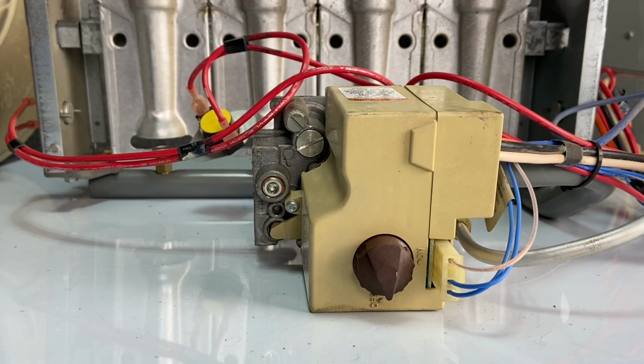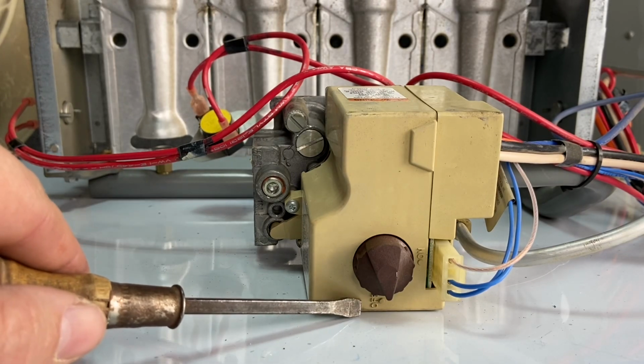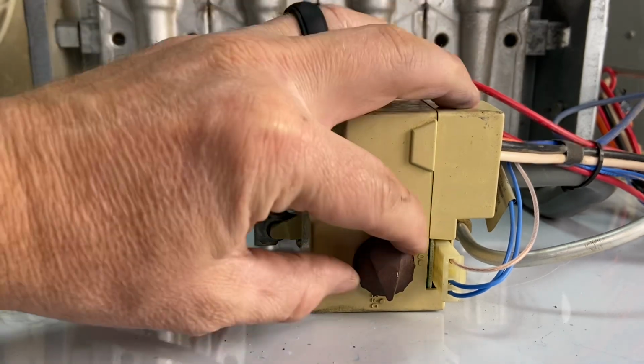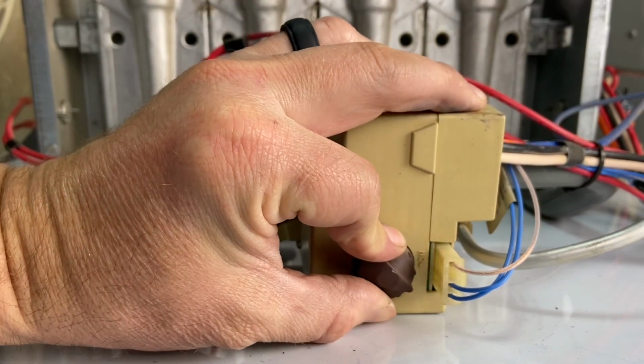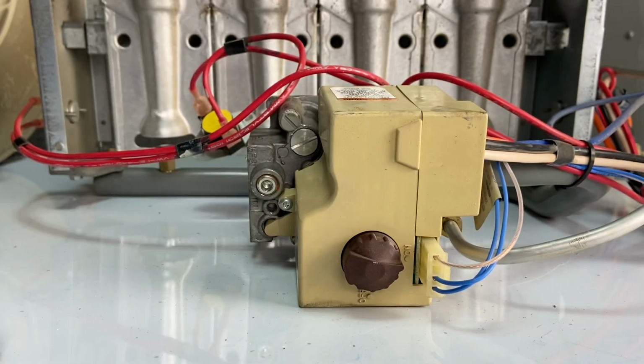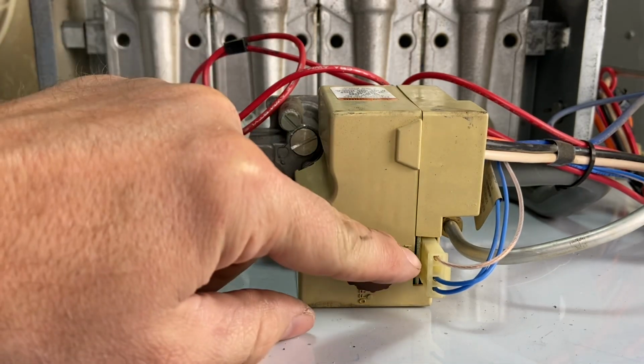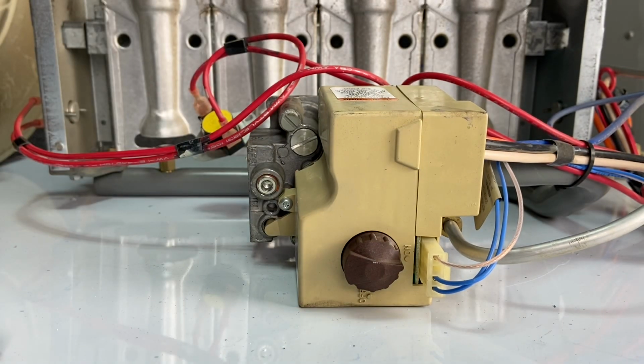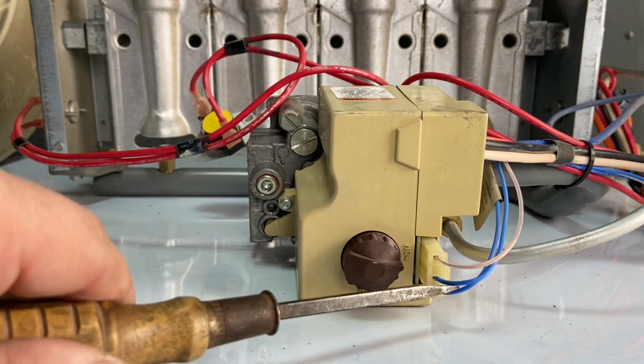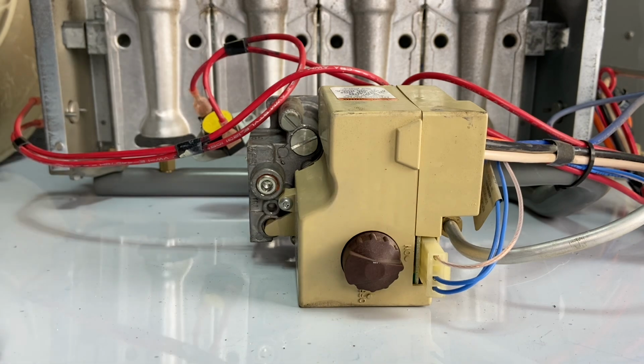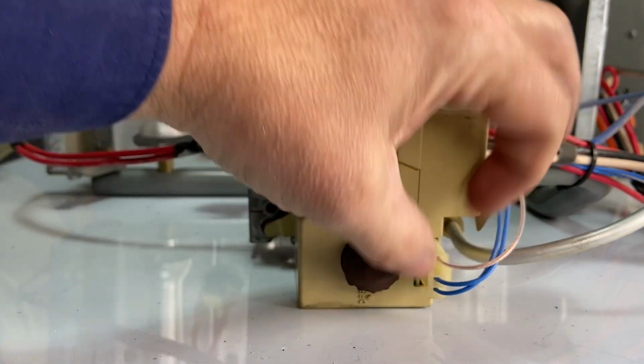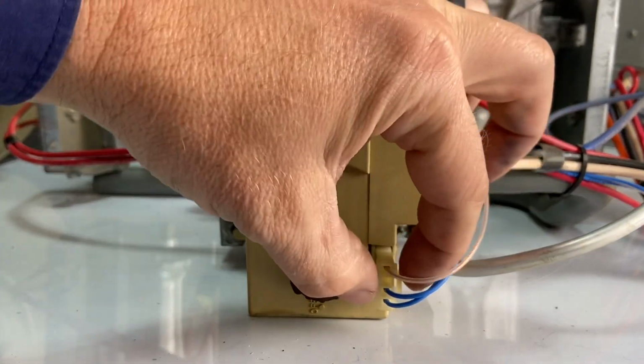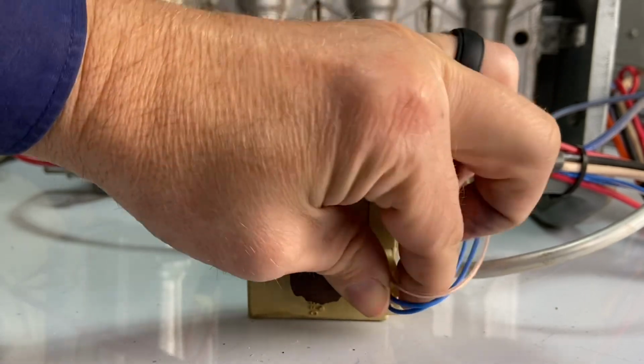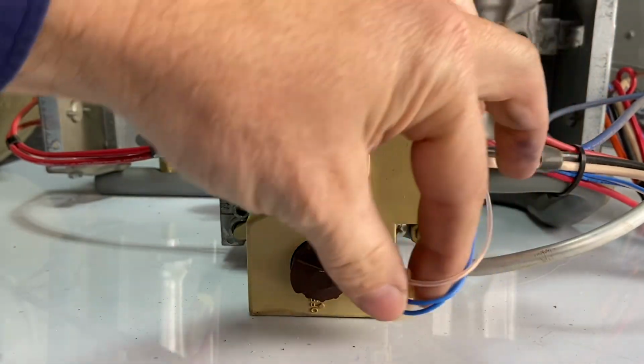So from this angle we can see our combination gas valve, or what they called a smart valve. This is our dial where we had off and on. If we wanted to leave it in the on position, we would have to turn this dial so that everything could actually light up. This plug right here is the plug for our hot surface igniter and flame sensor. The two blue wires are for the hot surface igniter, the single wire is for the flame sensor. There's simply a little keeper on the side. We push this keeper in, and this just unplugs, and we can replace that.